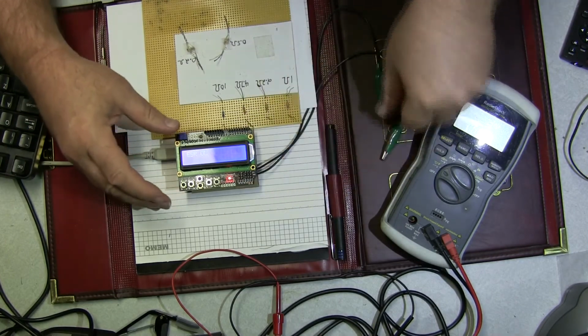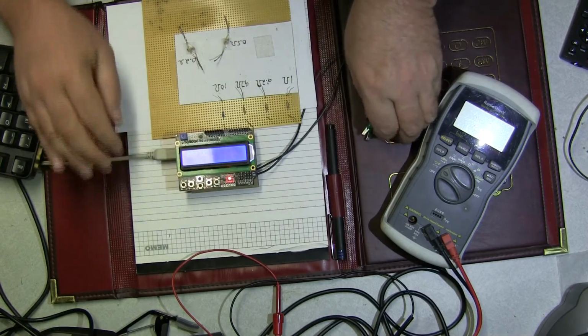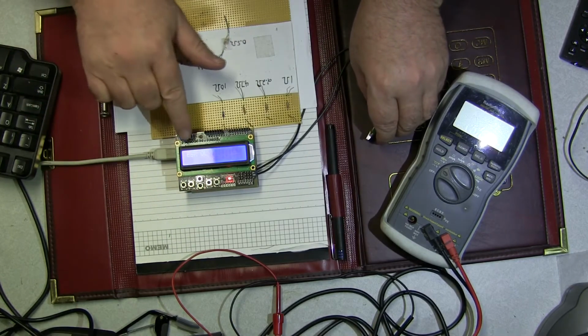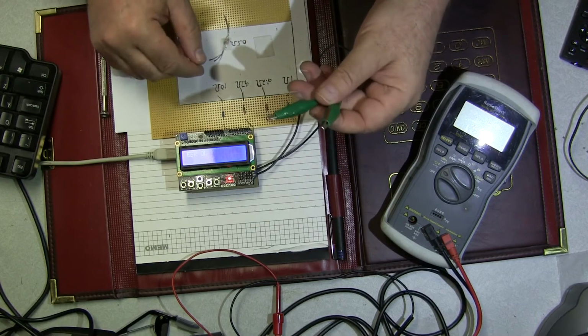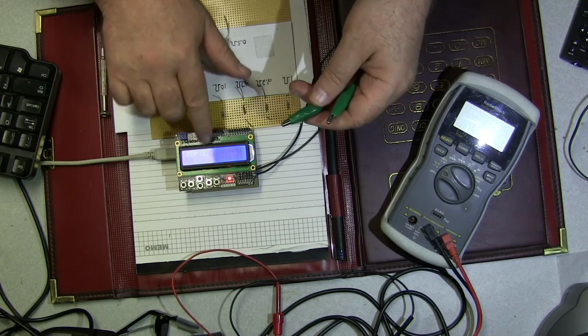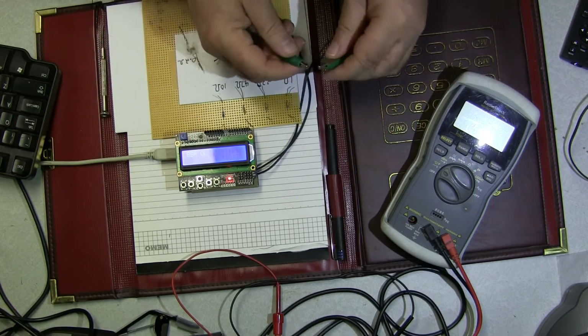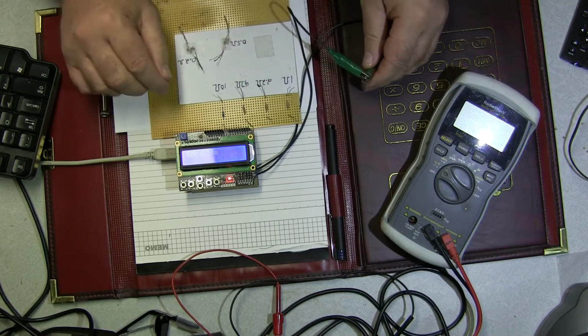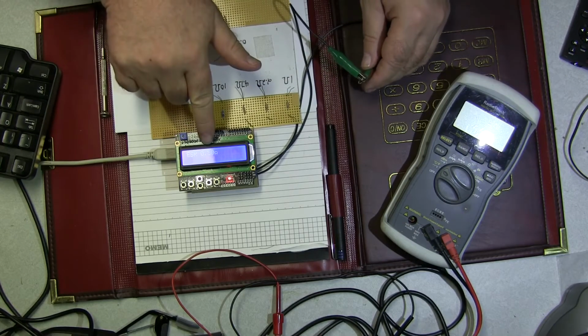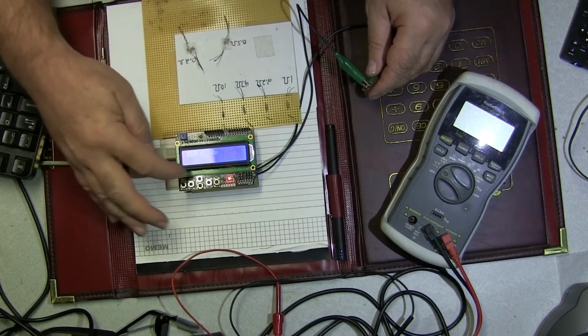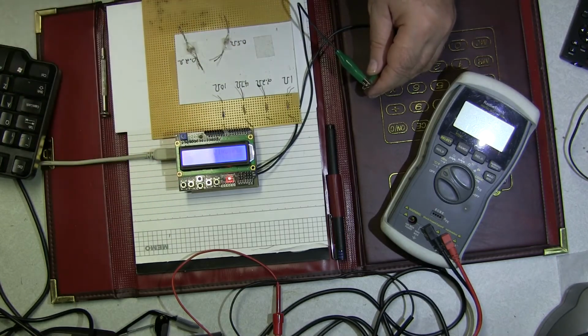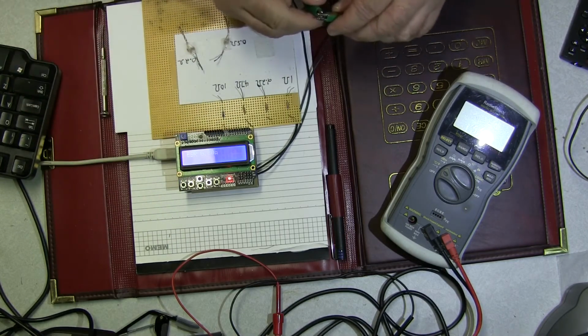We have the shield hooked back up now. Reset the shield, and it's going to read with our test probes open. It's going to show us an open loop. When we short together, we're out of calibration. It's showing us about 0.5 ohms, so we'll hit our calibration button, and it'll take us back and zero it out.